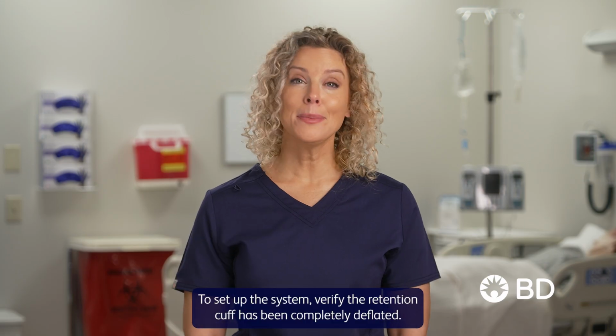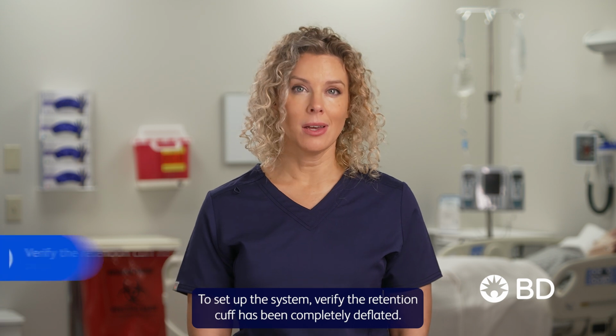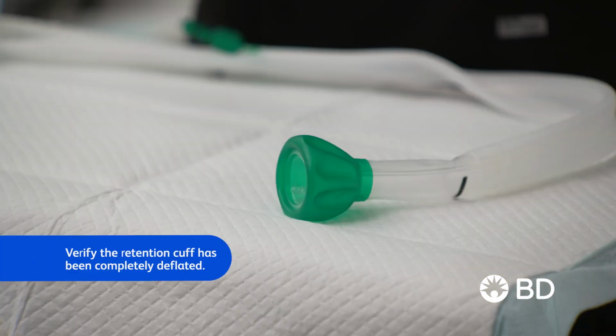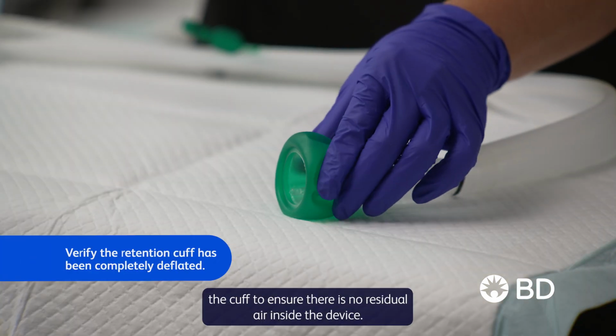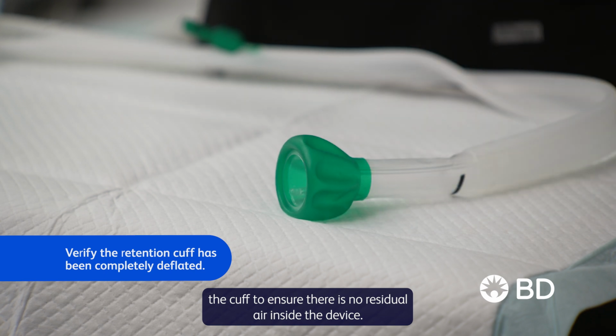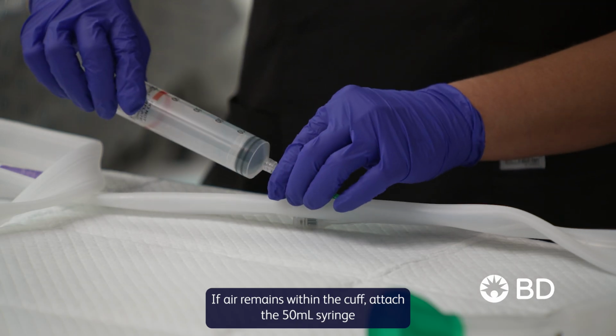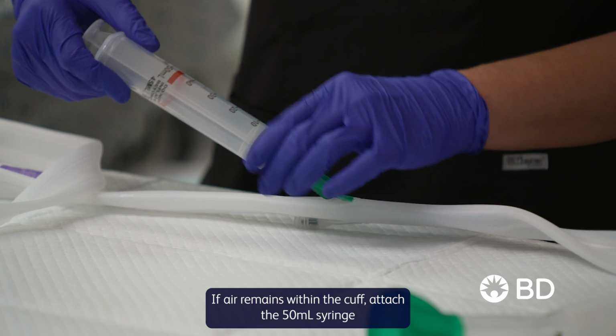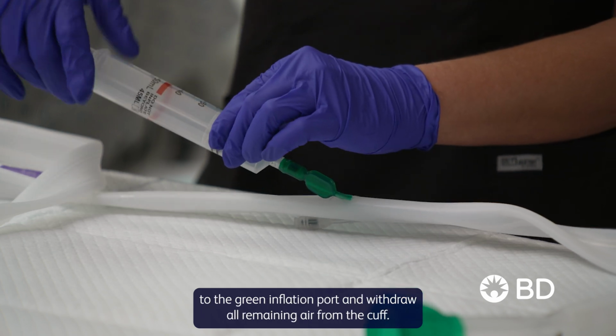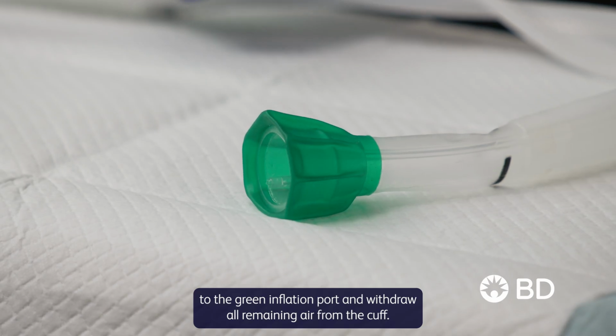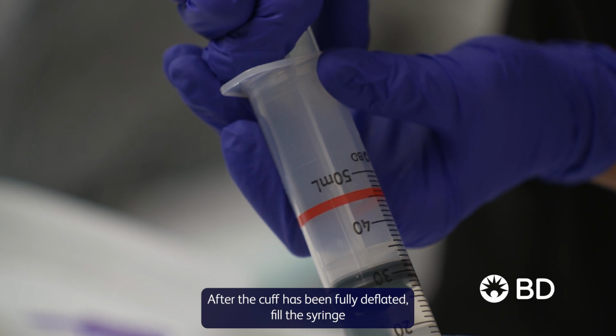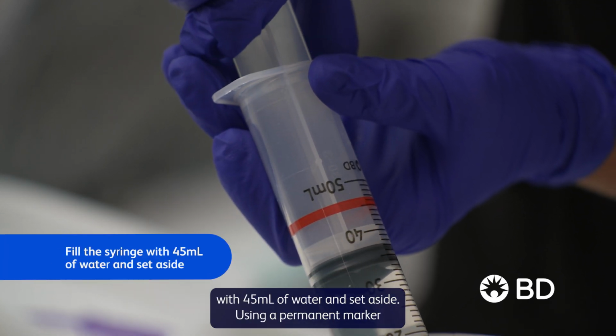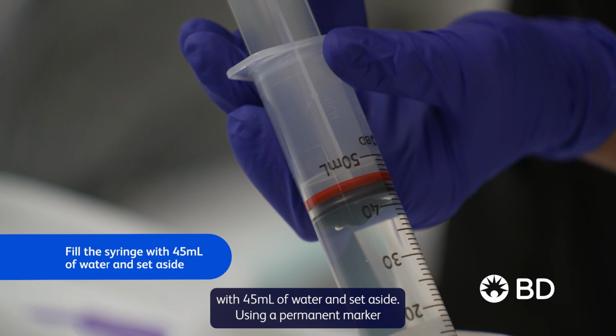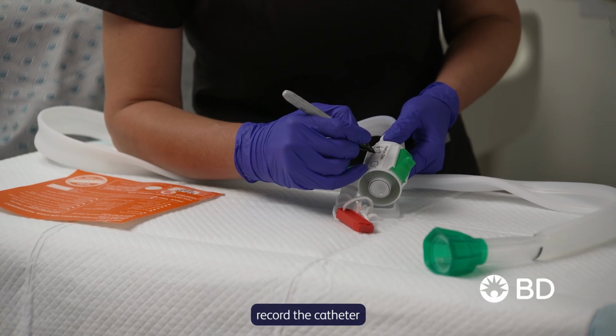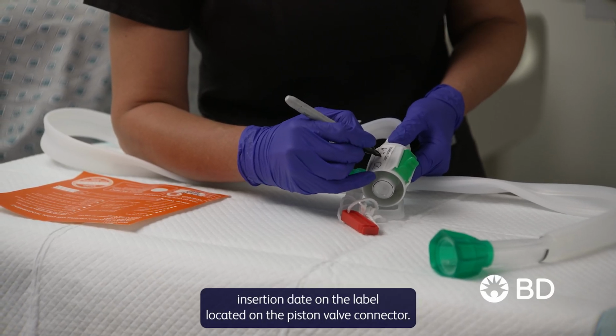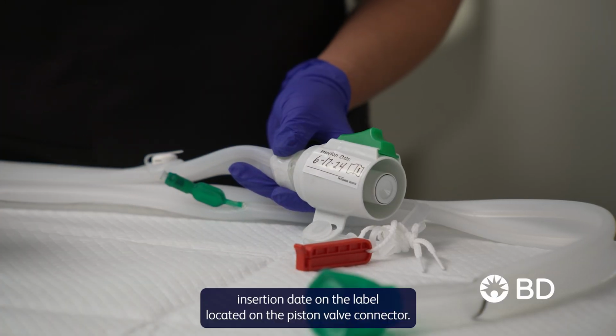To set up the system, verify the retention cuff has been completely deflated. This can be done by squeezing the cuff to ensure there is no residual air inside the device. If air remains within the cuff, attach the 50 milliliter syringe to the green inflation port and withdraw all remaining air from the cuff. After the cuff has been fully deflated, fill the syringe with 45 milliliters of water and set aside. Using a permanent marker, record the catheter insertion date on the label located on the piston valve connector.